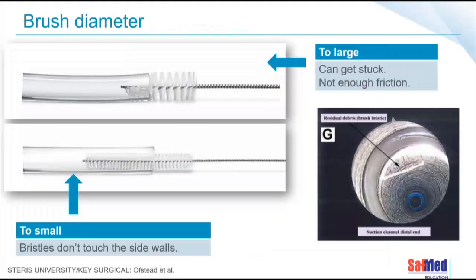When we're cleaning flexible endoscopes, it's really important that we use the right type of brush and the brush that's got the right diameter. If you have a look at the images on the screen, firstly, the image on the right over there, you can see a little bristle, and that's a piece of brush that's been left in a channel. That piece of brush can end up inside a patient. If we're using the wrong size diameter, a piece of bristle can break off. Or in fact, if we're using a brush that's gone through a lot of wear and tear.